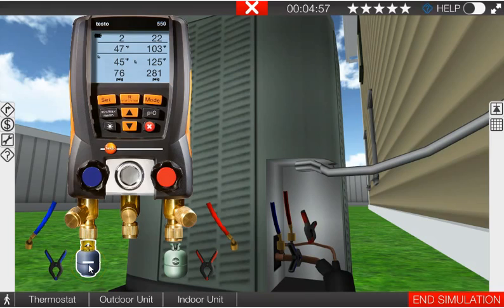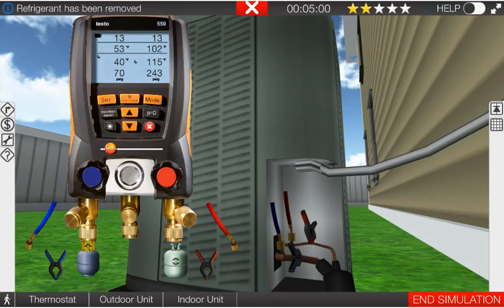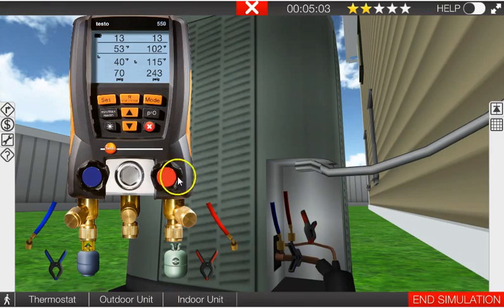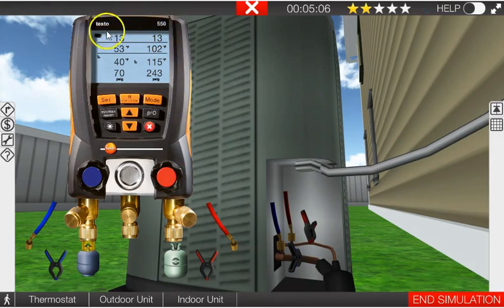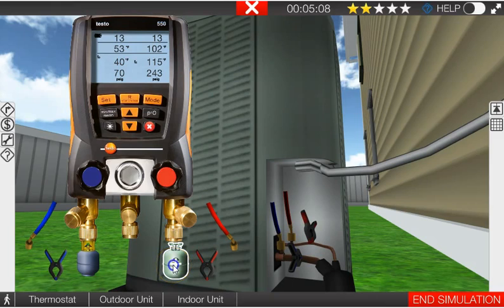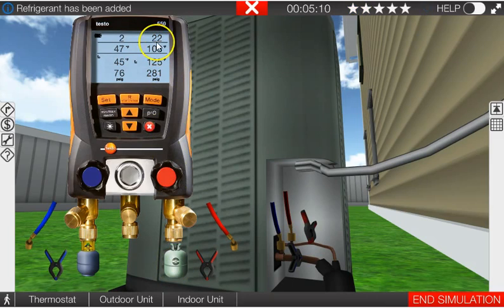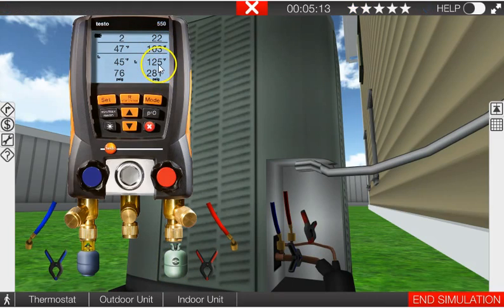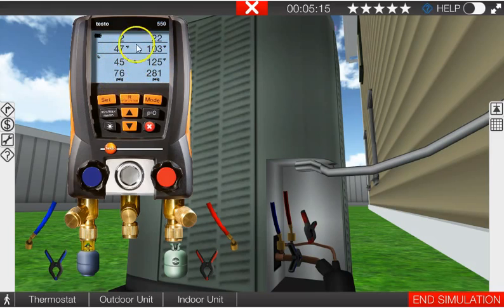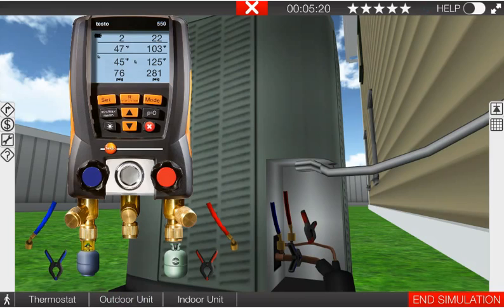All right, one more time. We'll go through it one more time so you get this. Here we are properly charged, good superheat and subcooling levels. And we overcharge the system. Subcooling increases, system pressures and temperatures increase on both sides, and our superheat decreases. That's what an overcharged system looks like.